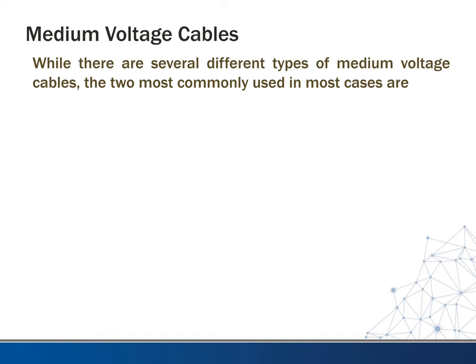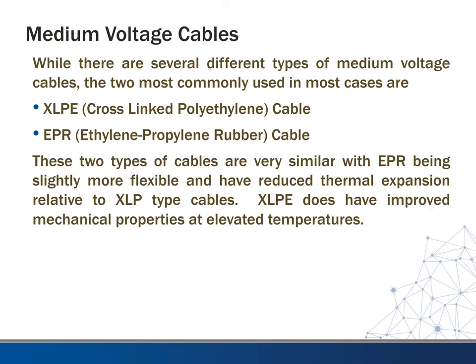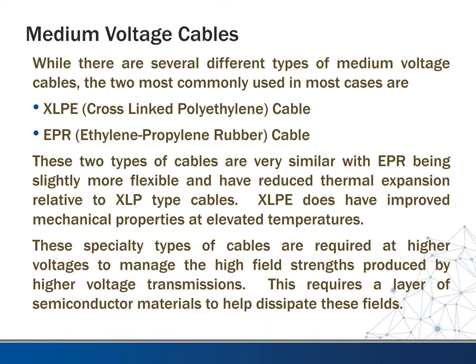I want to mention briefly medium voltage cable. This is usually outside the scope of electrical building design because we usually take it once it's stepped down to user voltage, but there may be instances where we have to do some medium voltage work. The two most commonly used types are XLP, or cross-linked polyethylene (XLPE), and EPR, which is ethylene propylene rubber cable. These two types are very similar, with EPR being slightly more flexible and having reduced thermal expansion relative to XLP. XLP does seem to have improved mechanical properties, especially at elevated temperature. Usually they are interchangeable, depending on the environment.